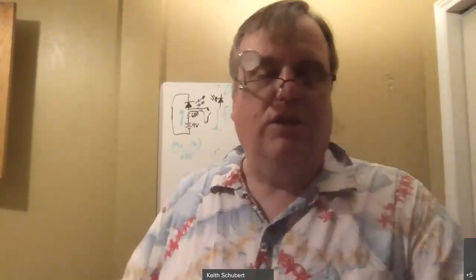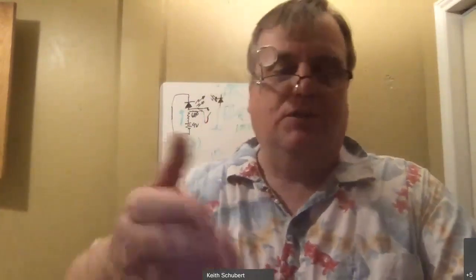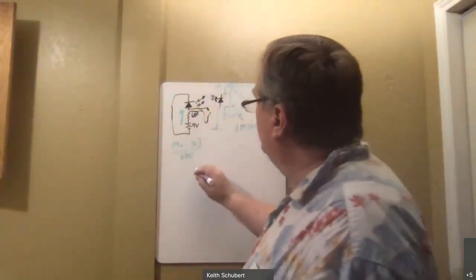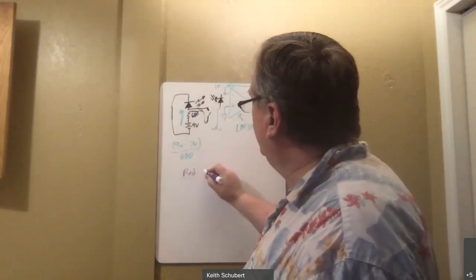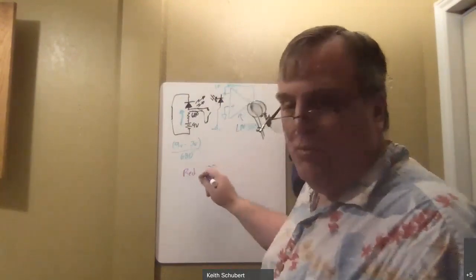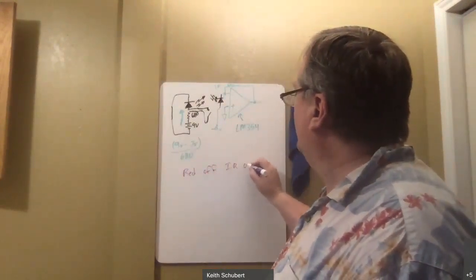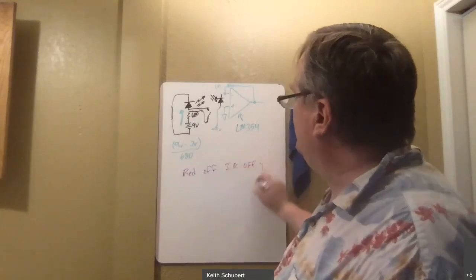But you also saw how you had to set the O-scope up to measure it. So remember, you have to do DC value. You can't do AC. And then basically the only difference to a regular pulse oximeter, besides a nicer surface mount instead of a toilet paper roll, is the timing sequence. I'm going to erase this so you can see it. You'll turn the red on and then both off. And then you'll do the infrared and then you'll do off and then you'll repeat.